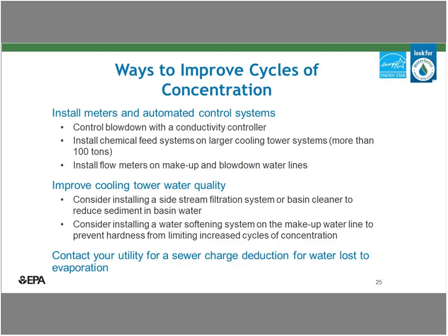In terms of retrofits to get the most efficiency from your tower, we've talked about some of these already, but install an automatic controller that operates the blowdown valve based on conductivity to allow yourself to maximize your cycles. Also install makeup and blowdown meters to track your water use on an ongoing basis. Monitor your trends and take corrective action if you need to. One important cost savings measure is that with appropriate meters, some utilities will let you deduct the quantity of water you evaporate from your sewer bill. These savings can be quite significant because cooling towers are big water users that evaporate a lot of water. So cost savings from a sewer deduction can be used to offset the upfront cost of installing meters and maybe purchasing other control mechanisms.